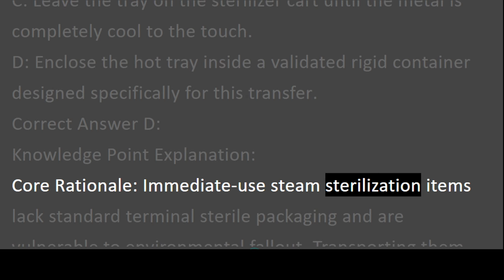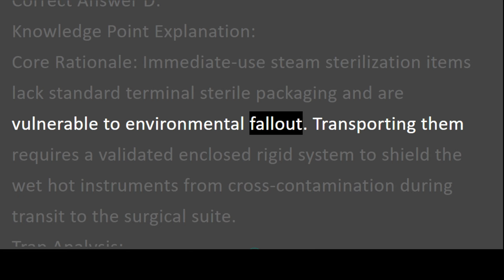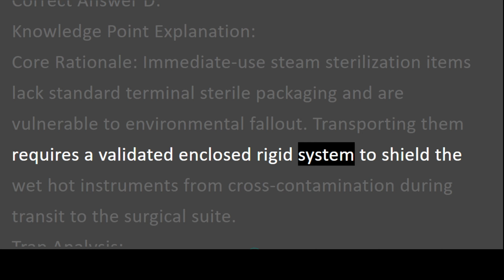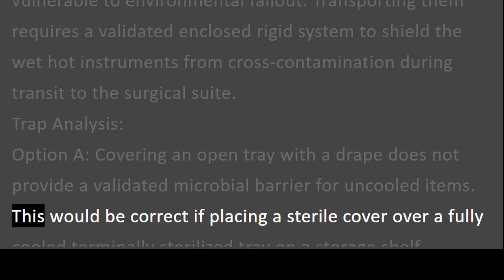Correct answer D. Knowledge point explanation. Core rationale. Immediate use steam sterilization items lack standard terminal sterile packaging and are vulnerable to environmental fallout. Transporting them requires a validated enclosed rigid system to shield the wet-hot instruments from cross-contamination during transit to the surgical suite. Trap analysis. Option A. Covering an open tray with a drape does not provide a validated microbial barrier for uncooled items. This would be correct if placing a sterile cover over a fully cooled terminally sterilized tray on a storage shelf.